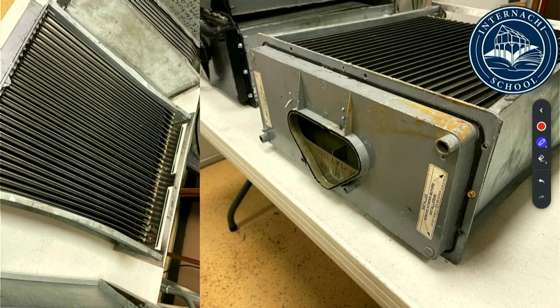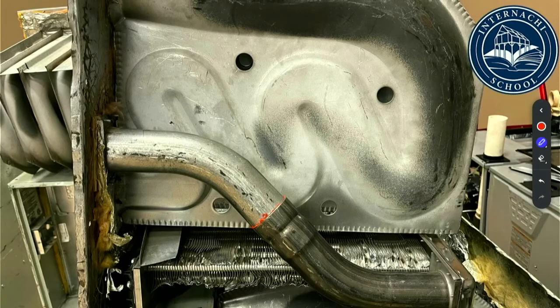Again, with the Carrier secondary heat exchangers, the biggest telltale sign, and I'm going to repeat it a few times, is when the furnace is running, if you get water dripping on the floor of that furnace or you start seeing stains, let it run for a while. Because if water's coming out of it, you got a hole in the heat exchanger. Even though the carbon monoxide detectors are not going off, that doesn't make it safe. You got a hole in the heat exchanger that needs to be fixed and replaced.